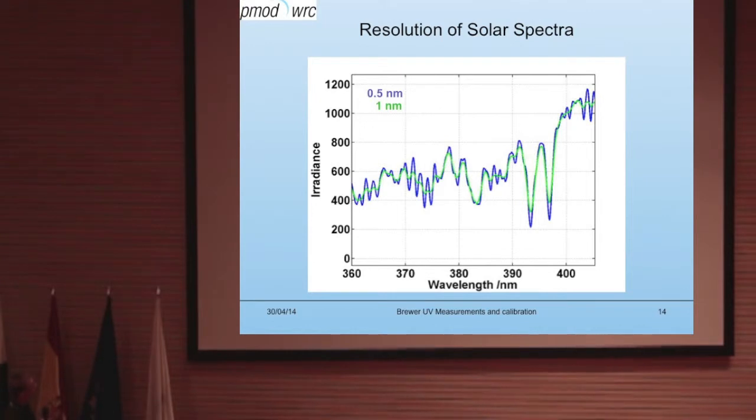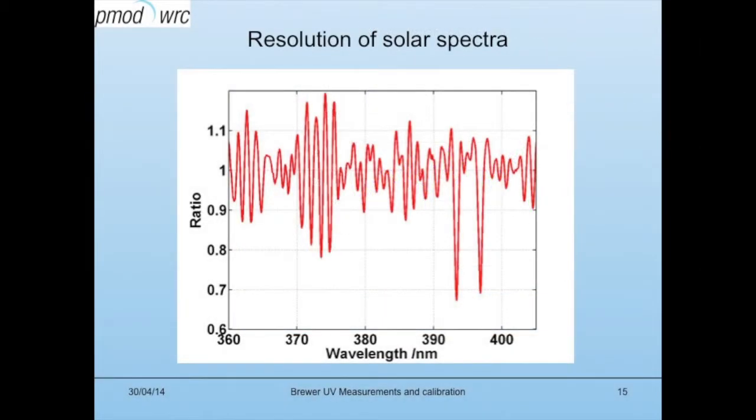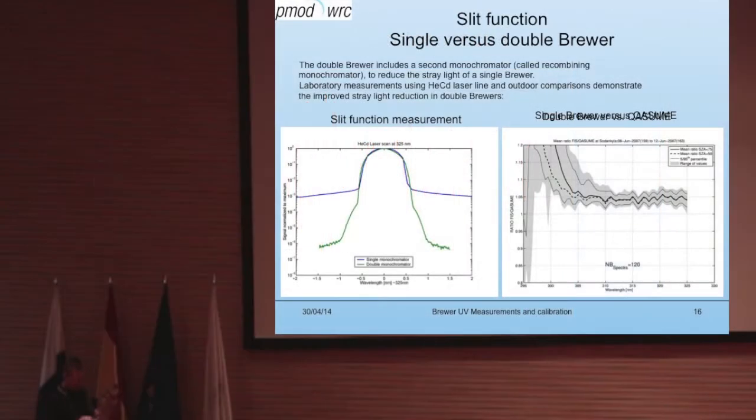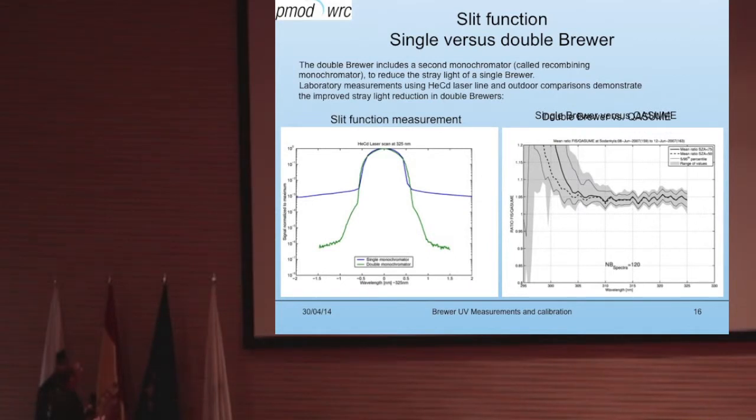And you can see already here, for a particular part of the solar spectrum, that these two instruments, even though they are measuring the same sun, will not be giving you the same answer for a particular wavelength. Then you will have this blue curve where you see that this instrument is behaving like a very nice instrument, allowing you to choose only the radiation for this particular area. But then about a factor of 1,000 less, you will see that all the radiation that is coming from the far end of the spectrum will still be able to get all the way through the instrument onto the photomultiplier.